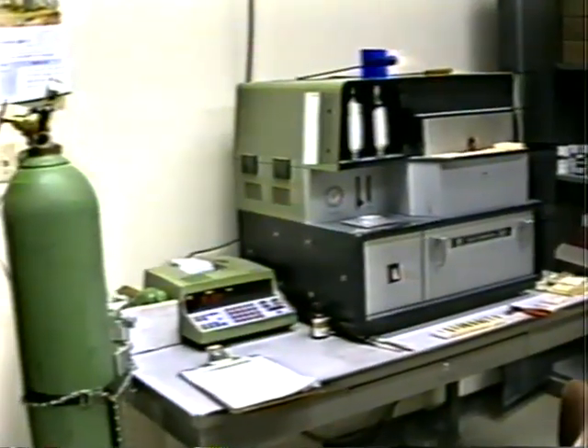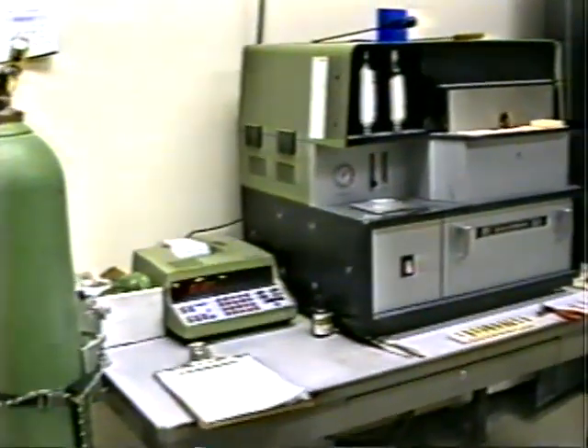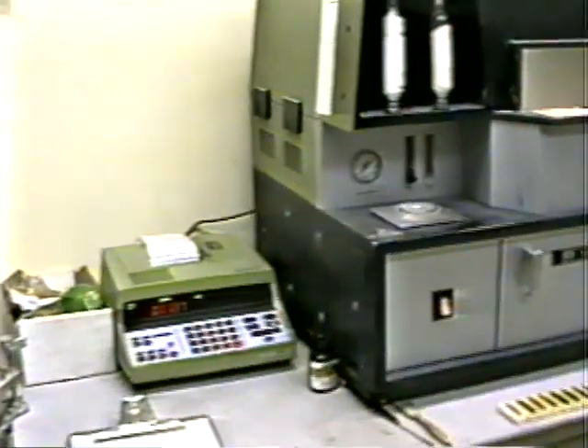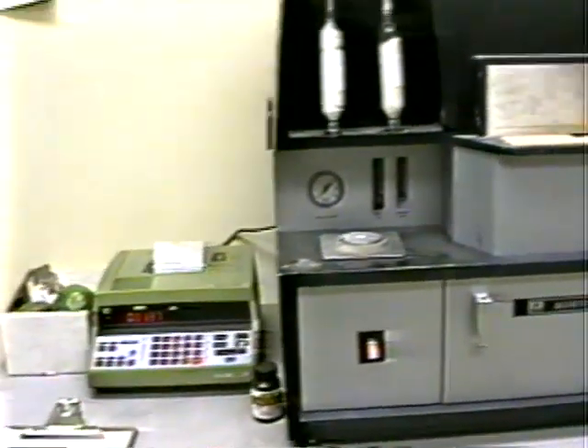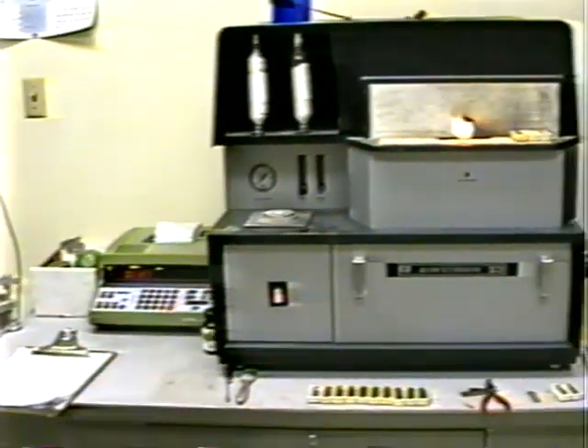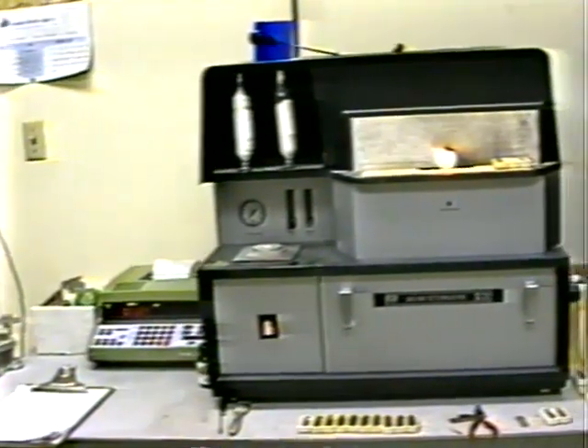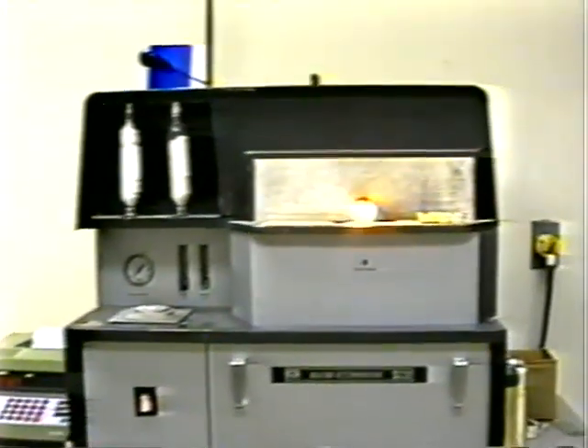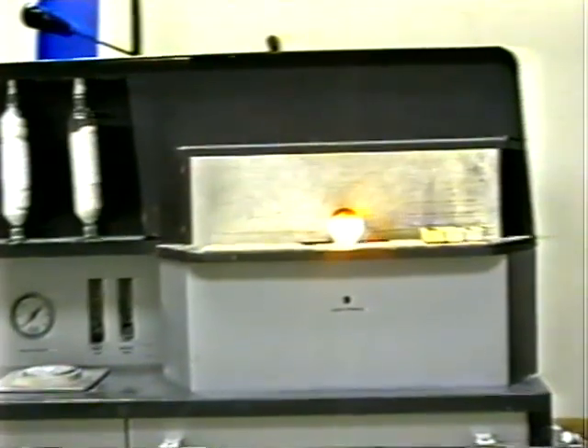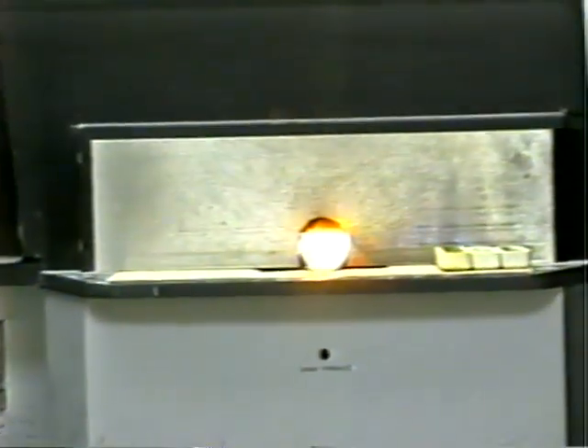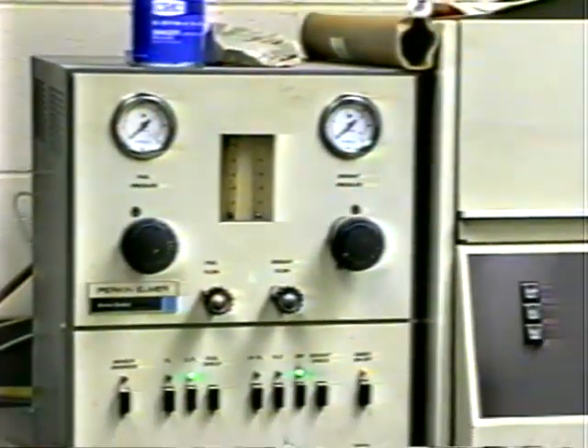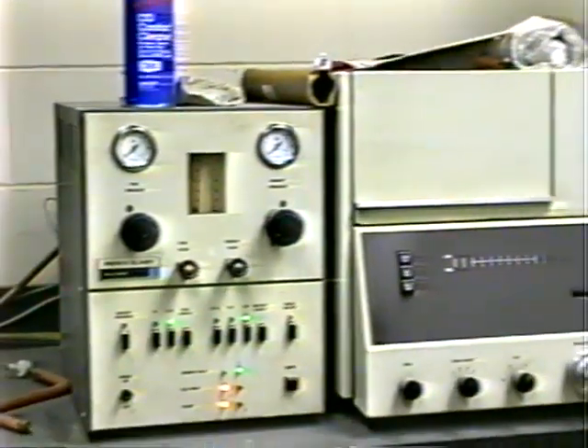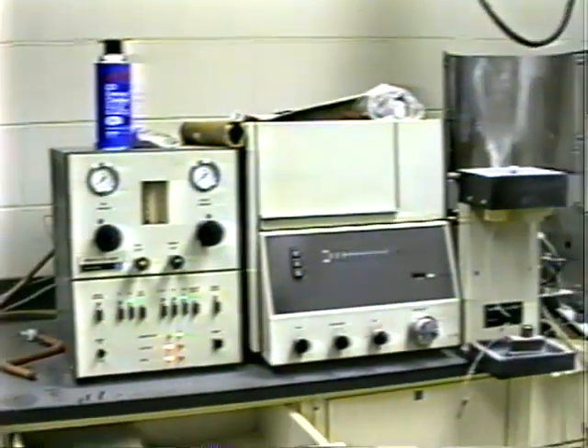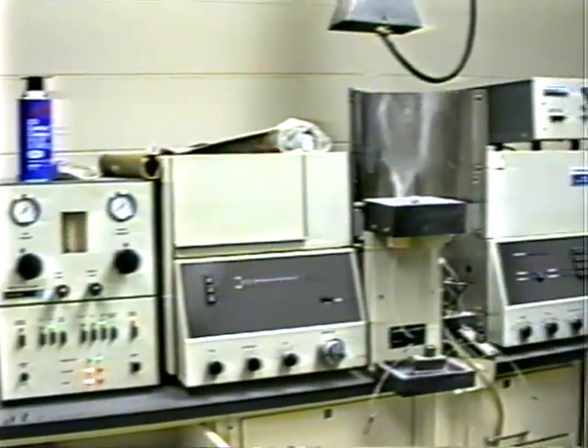Reviewing now is our sulfur analyzer, which is very critical to the operation of the concentrator. Oftentimes we dictate our reagent consumptions and things like that based off the amount of sulfur in our feed due to our low feed grades. Atomic absorption device, where we use this to come up with about 1/3 of our samples.